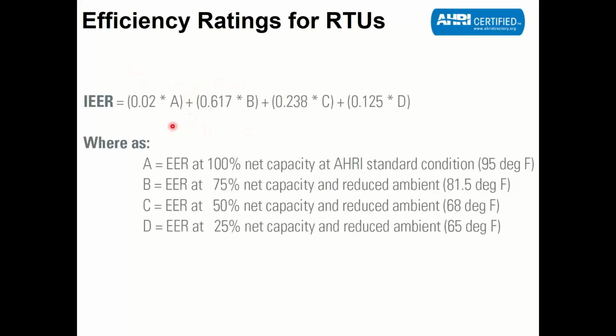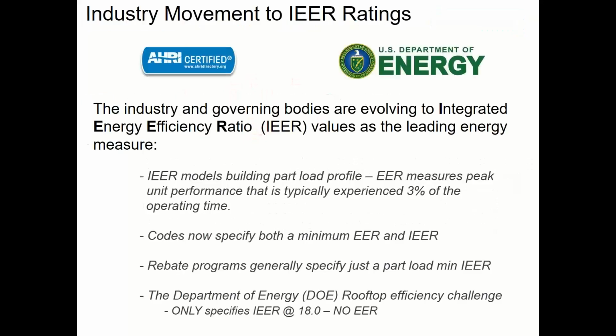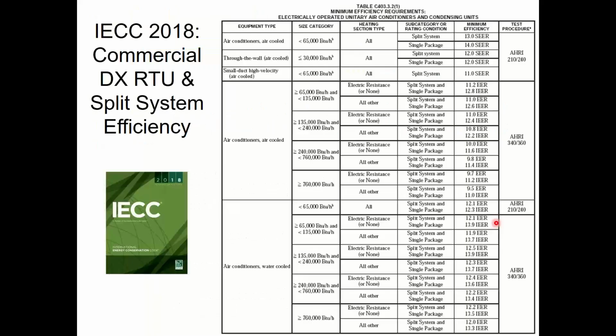We're basically saying full load doesn't matter because it hardly ever happens. Very low load doesn't matter because it's probably going to get free cooling from the economizer. So let's get efficient in this middle range here. That's just explaining kind of what that is. Not only do the energy codes now include IEER, but the Department of Energy metrics no longer have any EER at all. They don't even look at full load in any way whatsoever. It's all part load efficiency because full load is old and irrelevant.